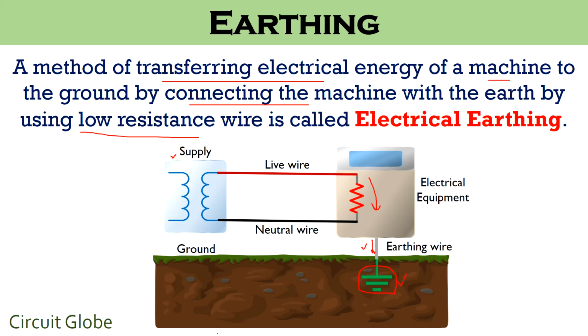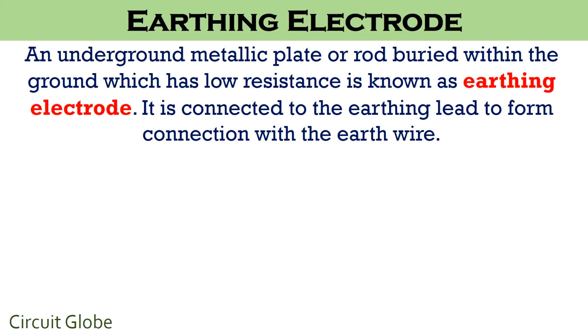So let's understand more about the earthing electrode. An earthing electrode is a metallic plate which is present within the ground and has low resistance. It can be in the shape of a pipe, plate or rod, and through this rod the fault current flows through the ground safely. To form a connection between the earthing electrode and the earth cable, an earthing lead is used. This acts as the joint between the wire and the electrode.